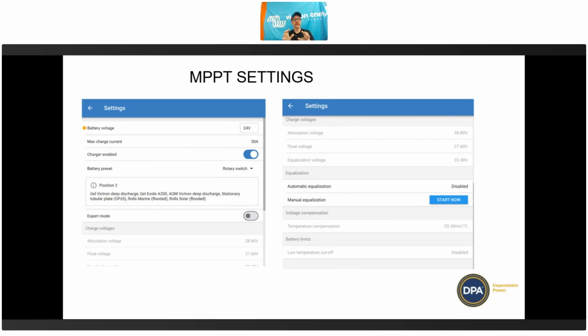That will convert it from being a preset to a user-defined setting, but the template will be there for you. So if it's a tubular plate gel, it's going to have all the equalization options that you need for a tubular plate gel, and then you go and check those against the manufacturer's instructions. If it's lithium, it's going to turn off automatic equalization.